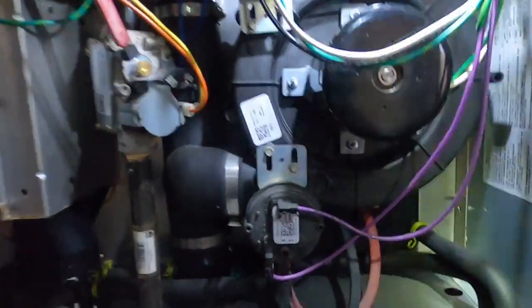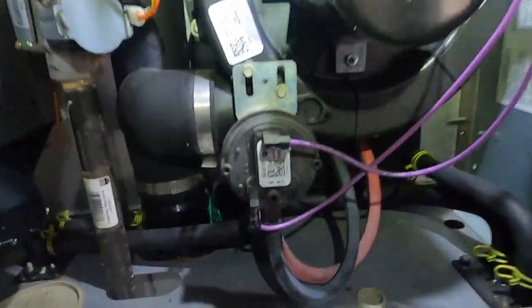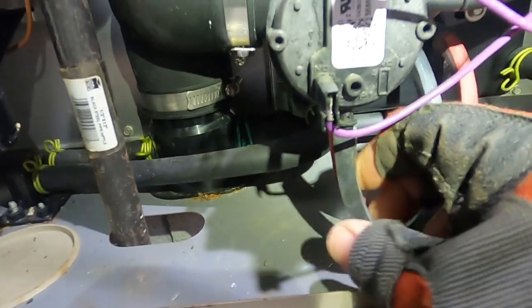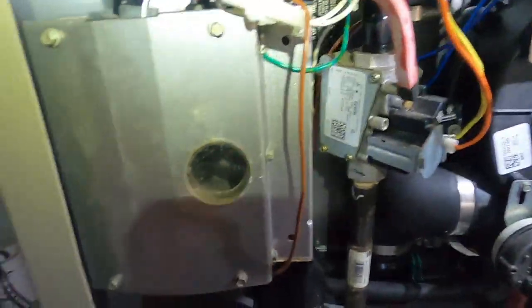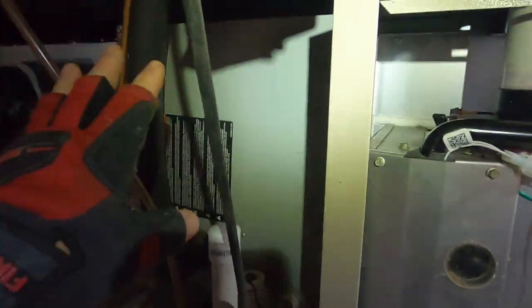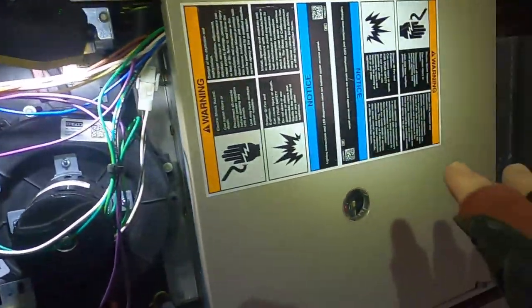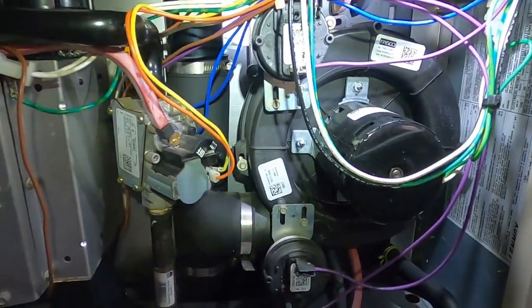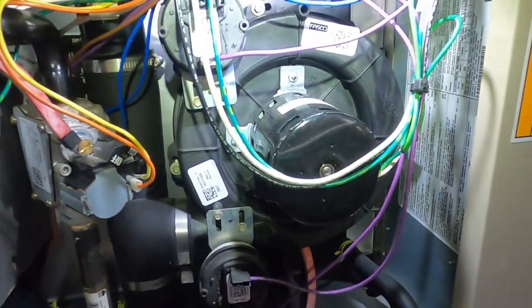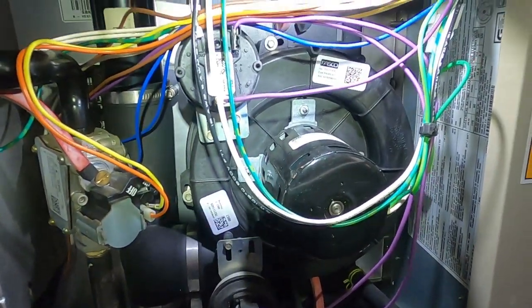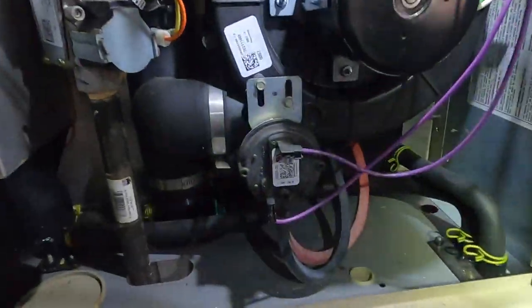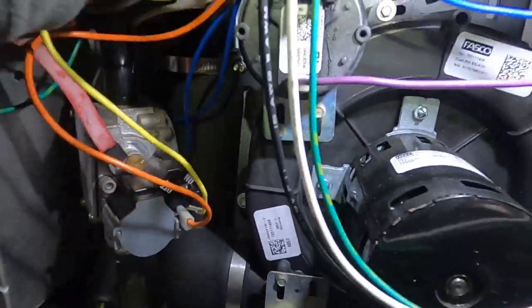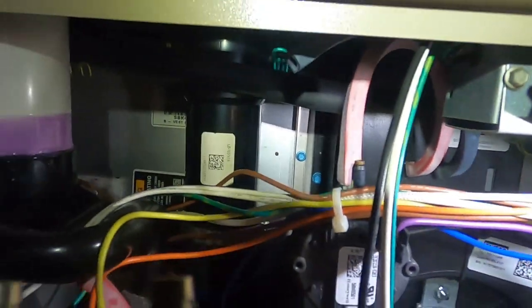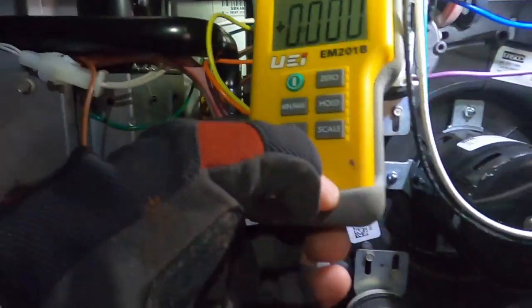So what I'm going to do real quick is go around to each one of these switches, pull these hoses off, and turn the blower on. I've got a sealed box over here. Got the coil door back on, blower door back on, at normal operating static, whatever that is. I hadn't checked static on it. I'm not going to do that. But I want to see if I get a pressure change when that blower comes on. I'm just trying to come up with some ideas.